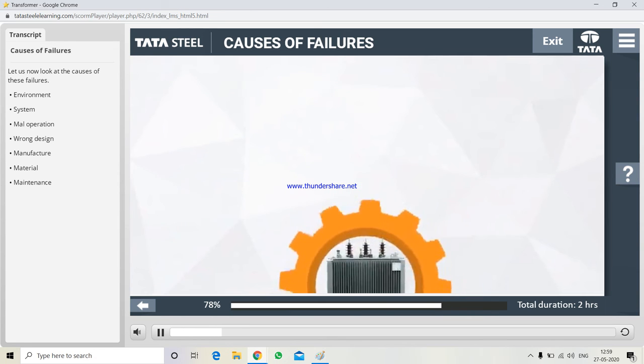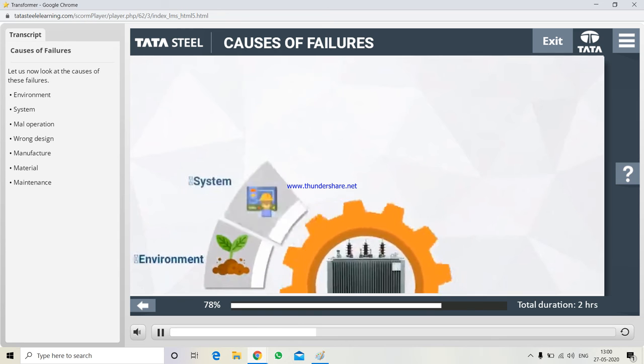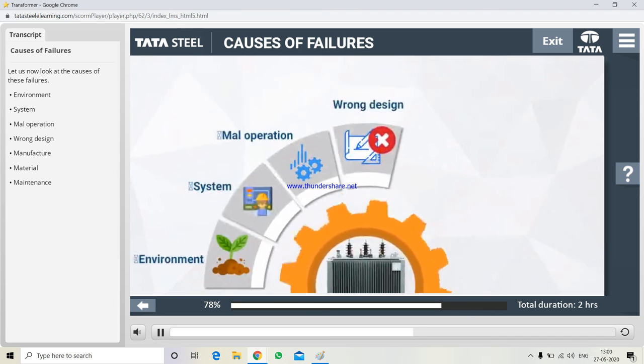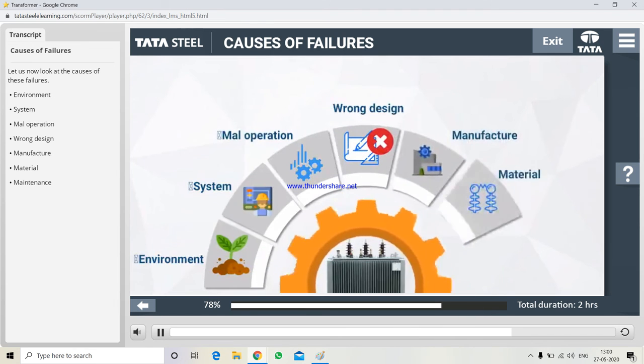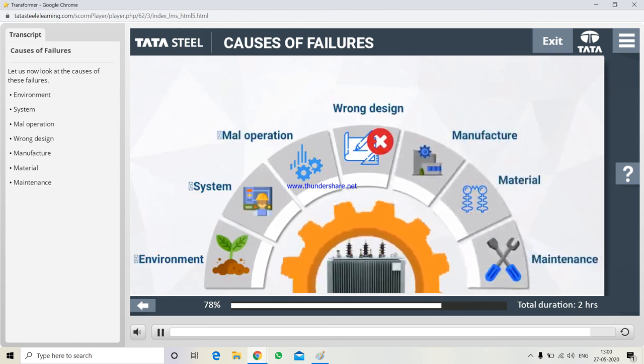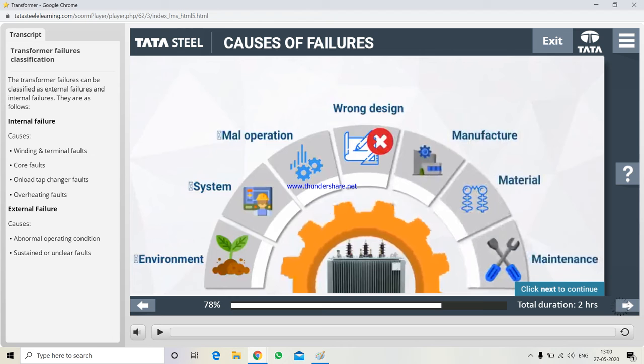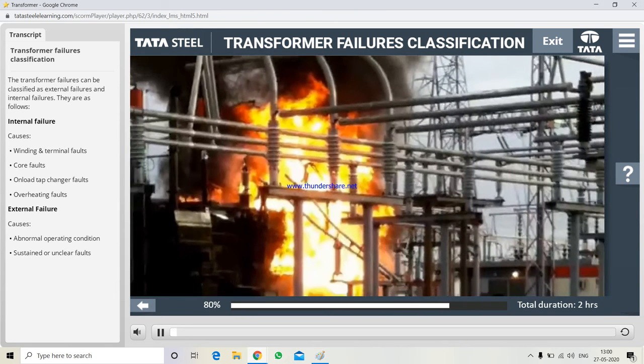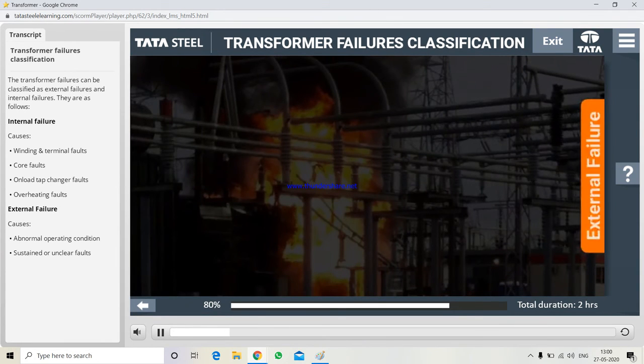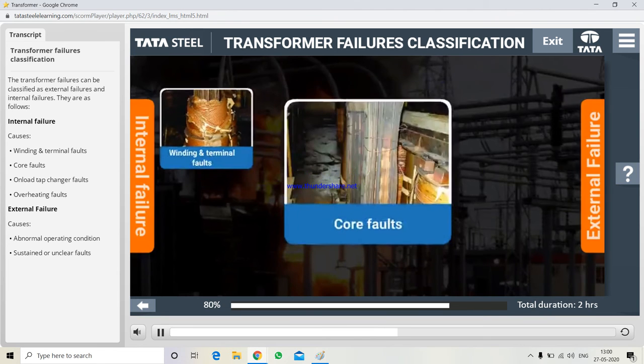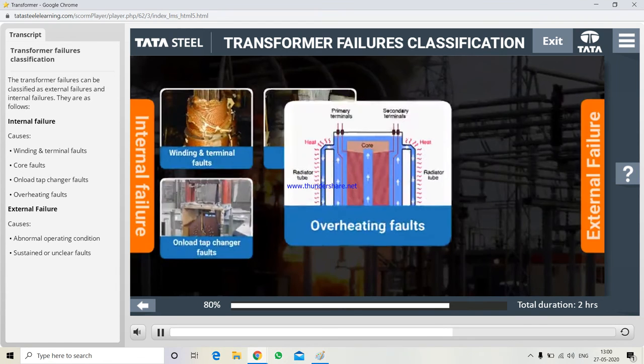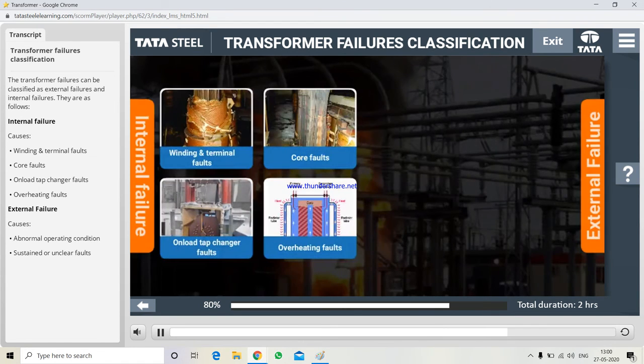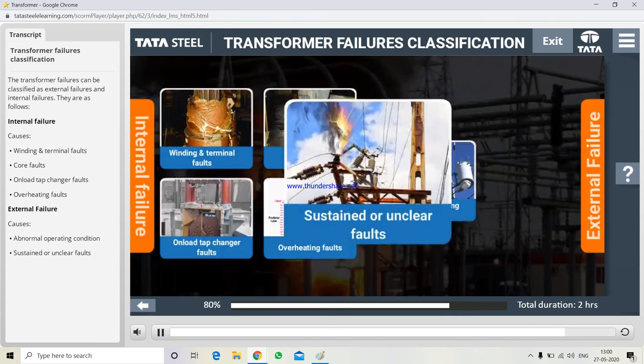Let us now look at the causes of these failures. Environment, system, maloperation, wrong design, manufacture, material, maintenance. The transformer failures can be classified as external failures and internal failures. They are as follows. Internal failure causes: winding and terminal faults, core faults, on-load tap changer faults, overheating faults. External failure causes: abnormal operating conditions, sustained or uncleared faults.